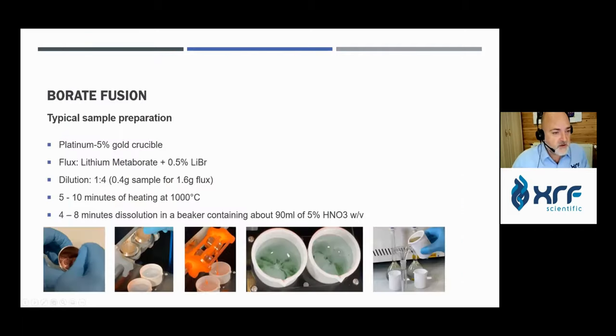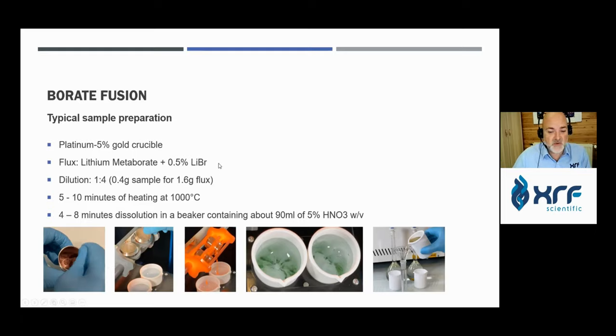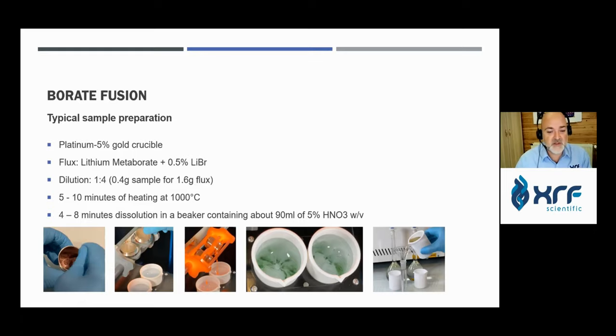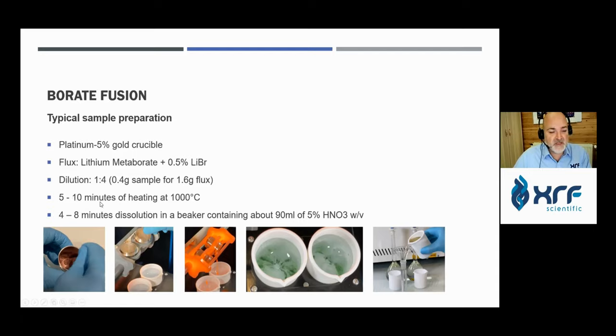For a typical borate fusion sample preparation, platinum-gold crucibles are used. The flux is lithium metaborate or lithium tetraborate — the most commonly used is lithium metaborate — with lithium bromide added as a non-wetting agent to ensure all product pours out of the crucible. Typical dilution is 1:4 up to 1:10; for example, 0.4 grams of sample with 1.6 grams of flux, dissolved in a 100 mL beaker. Fusion is done at approximately 1000°C and takes about 5 to 10 minutes of heating, with dissolution taking 4 to 8 minutes in the beaker.